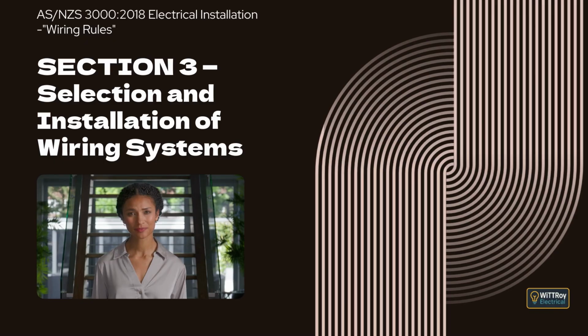Where substantial harmonic currents may be present, such as from nonlinear loads, the third and higher order harmonic currents in the neutral must be taken as 100% of the highest load generated harmonic current on any phase. In consumer mains, submains, and final subcircuits, the current carrying capacity of the neutral conductor must not be less than that of the largest associated active conductor. Certain exceptions are allowed where abnormal conditions or protective arrangements limit the neutral current.